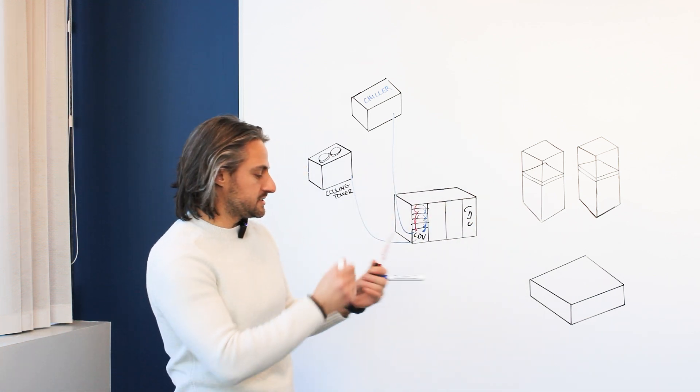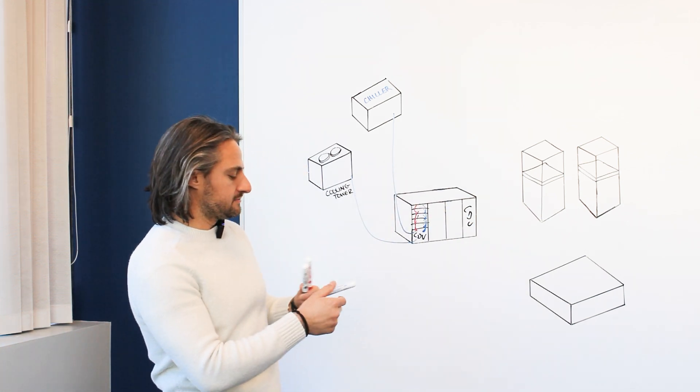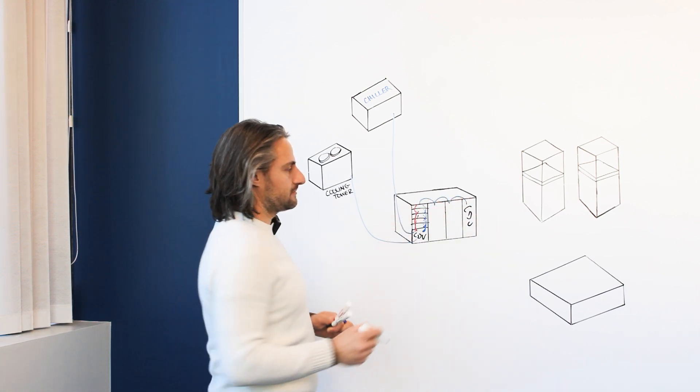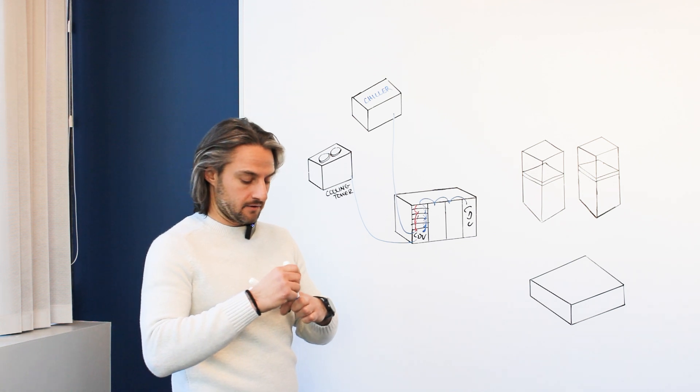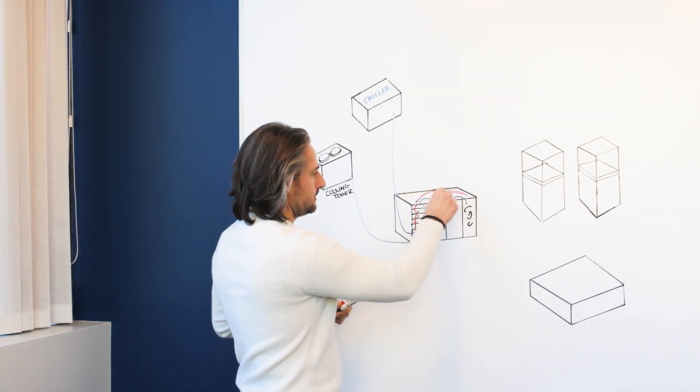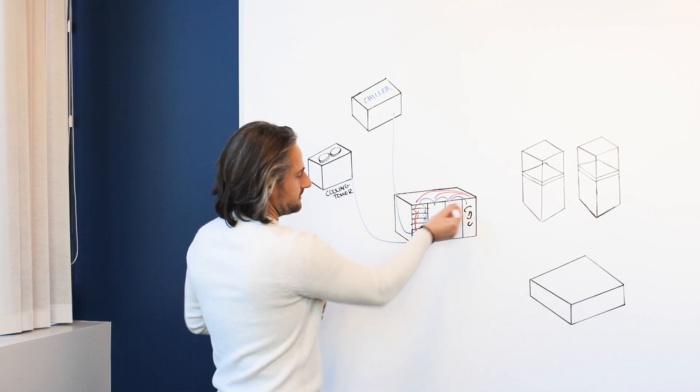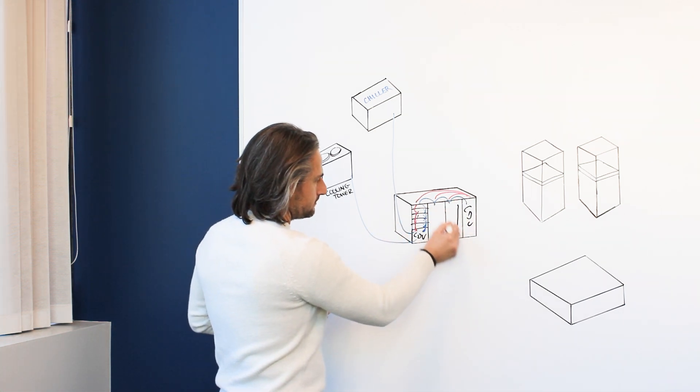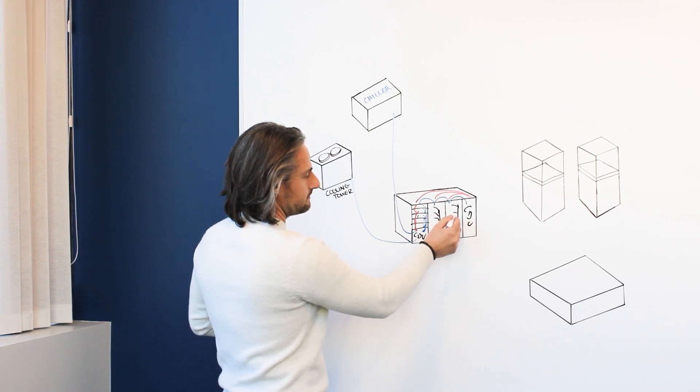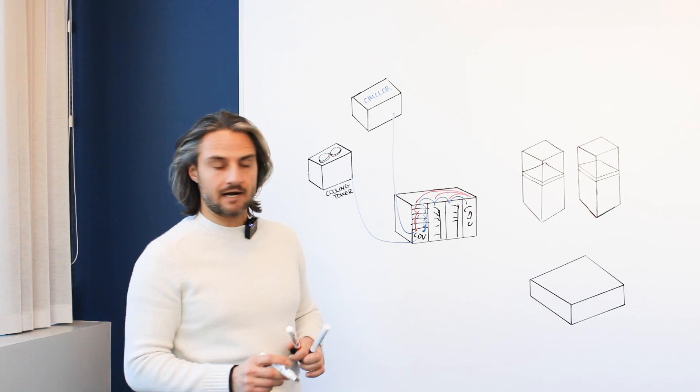So this CDU is doing very similar work to the in-rack, except that now it's distributing coolant to all of the server racks that are in that row, in parallel, and collecting all of the heat from each of those server racks coming back. So inside of each rack, we then have a manifold that's distributing the fluid to all the servers that may be in that particular rack.